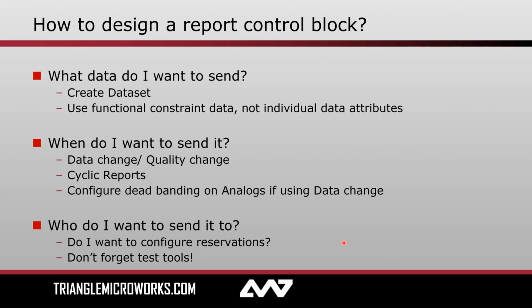Now moving over to kind of a practical standpoint, what do you need to keep in mind? If you are designing a digital substation, specifically the SCADA portion, the data that's going to be passed up to your clients, what do you need to keep in mind? Well, the first thing you need to do is decide, what data do I want to send? And this is the act of creating a data set. Now, as I mentioned before, you'll want to include data objects in that data set. This is a best practice, not a requirement, but it is definitely the recommendation to include entire data objects with a functional constraint. So when you do that, as I said before, you'll get quality and timestamp along with status value.